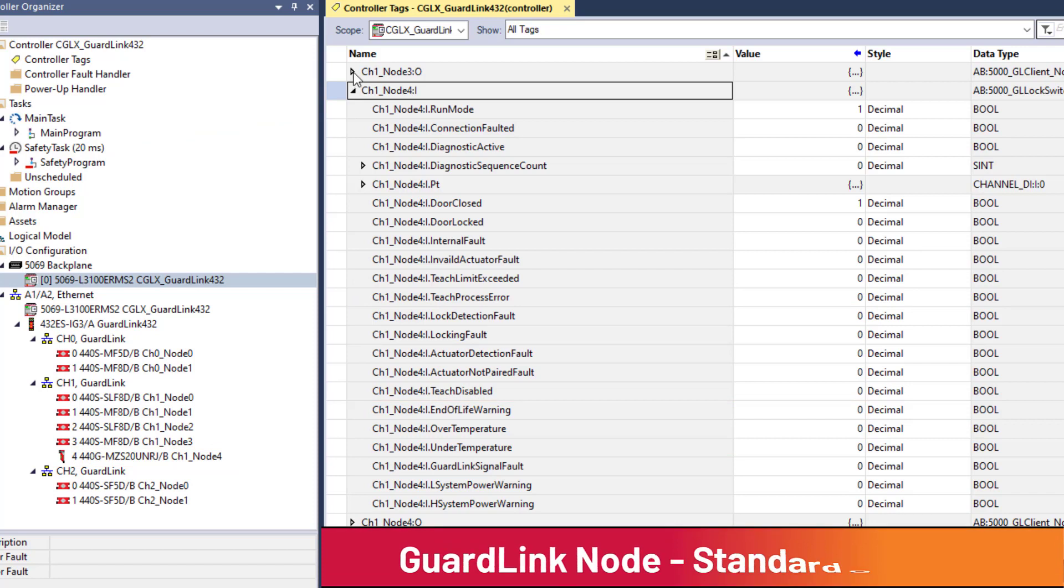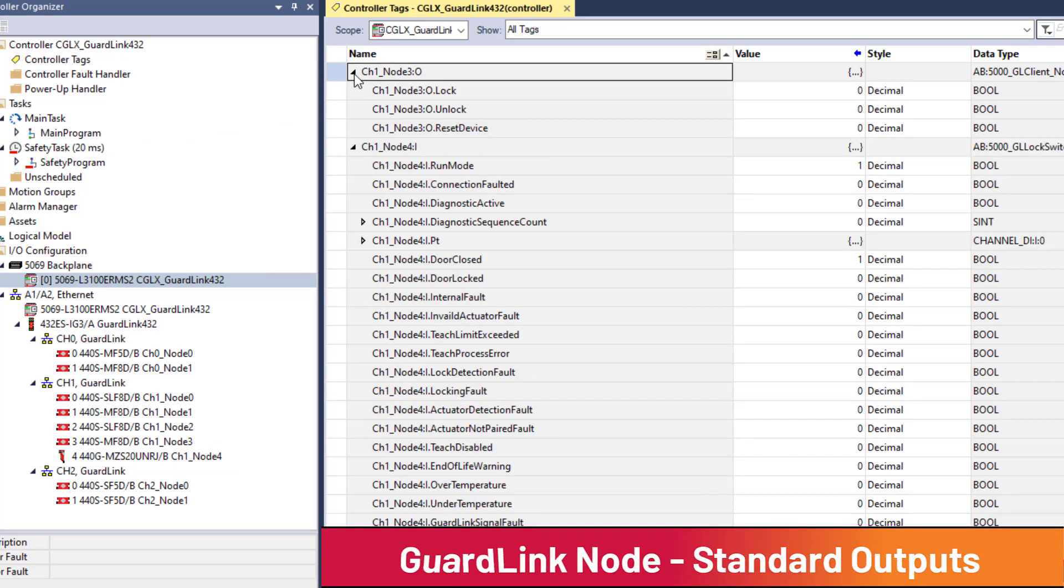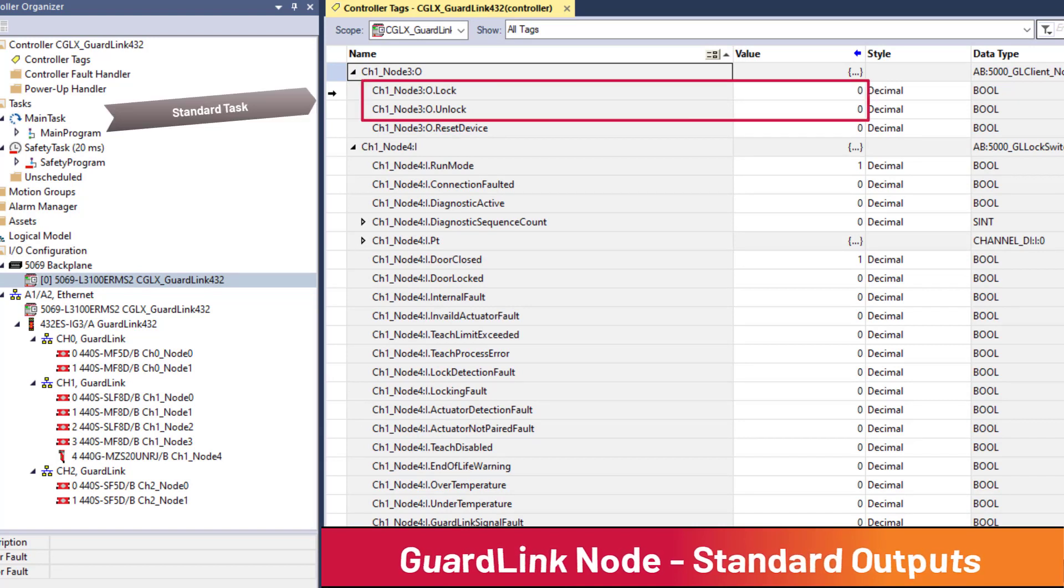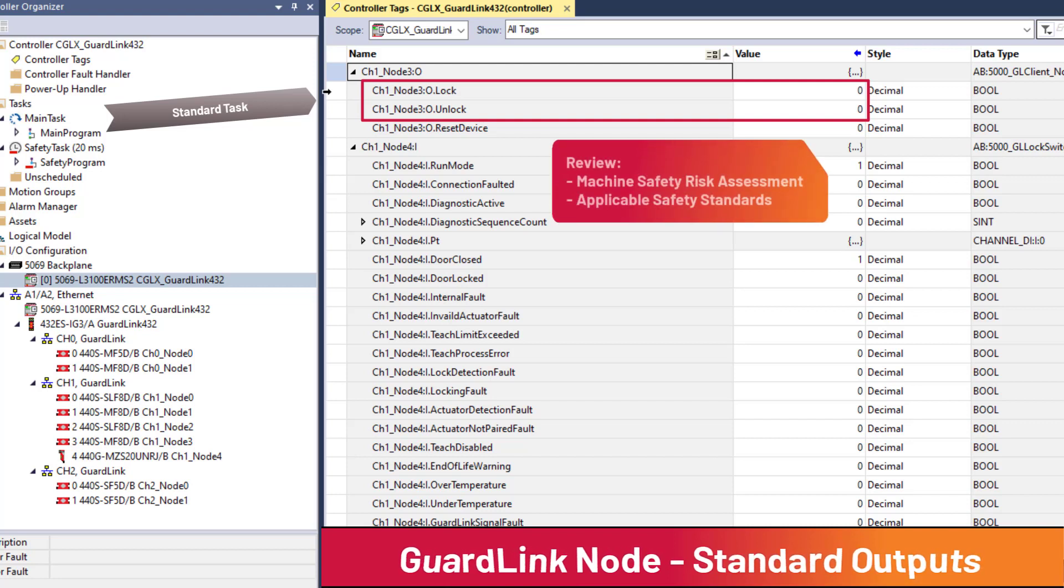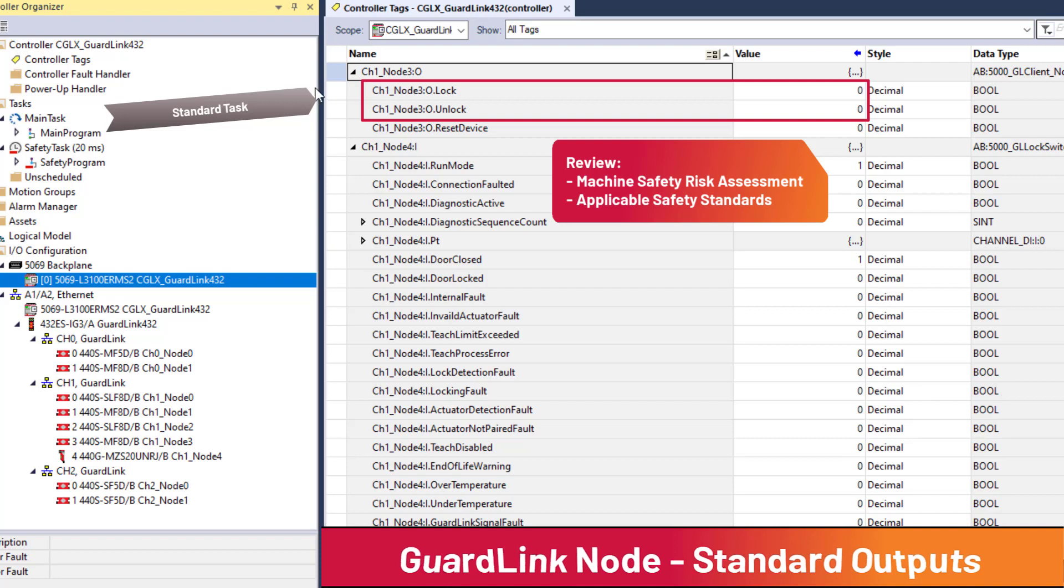Each GuardLink node has a standard rated output tag. Locking guard doors can be locked or unlocked from standard logic using the GuardLink interface. Unlocking guard doors from the standard task may not be justifiable for safety rated locking functions. Review the machine risk assessment and appropriate interlock safety standards like ISO 14119 before using the non-safety rated guard door locking feature.